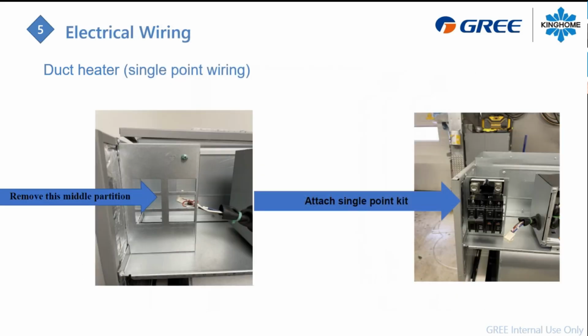When you attach a single point connection, you will have to remove this small piece of metal here on the plate right here. You need to make sure your breaker is side by side and touching together to make a good connection with the single point here. So now, in a case that it's, for example, a 20 kilowatt, like most of the Quebec installation here, you need to provide a big wiring on those screw here to make sure you power the unit correctly.